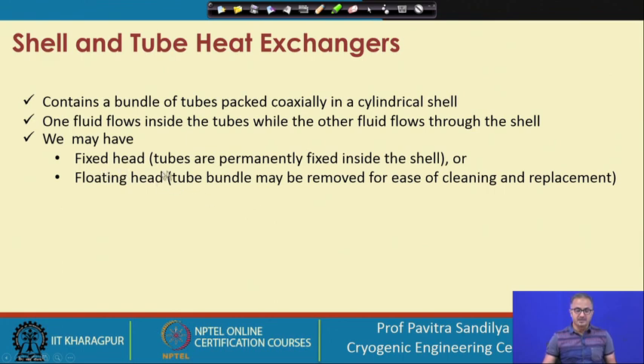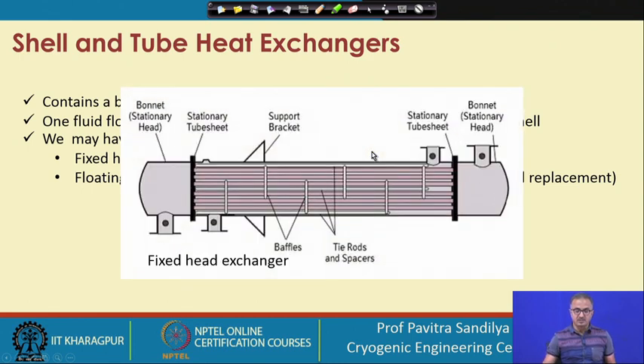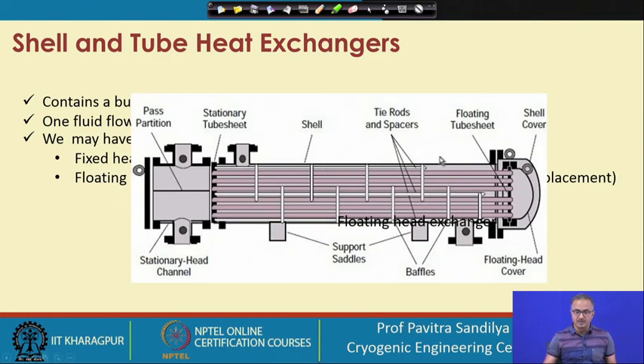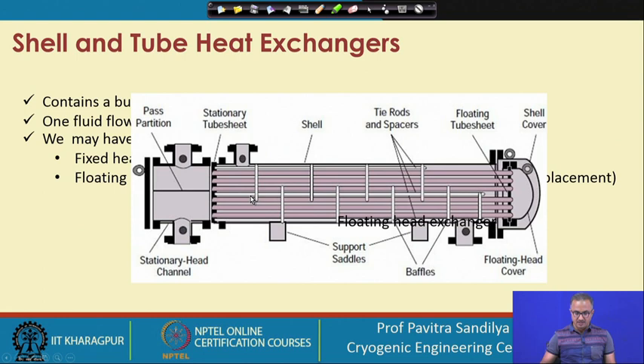Shell and tube heat exchangers may have a fixed head, where tubes are permanently fixed inside the shell, or a floating head, where tube bundles may be removed for ease of cleaning and replacement. In the fixed head configuration, stationary heads are on both sides along with baffles and tie rods. In the floating head configuration, the head can be taken out of the shell for maintenance or replacement and put back after cleaning.